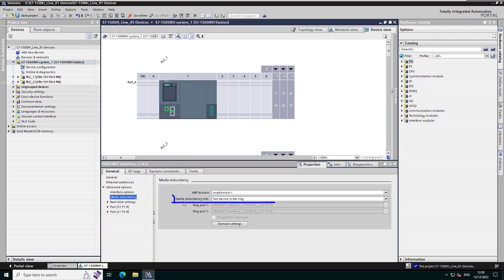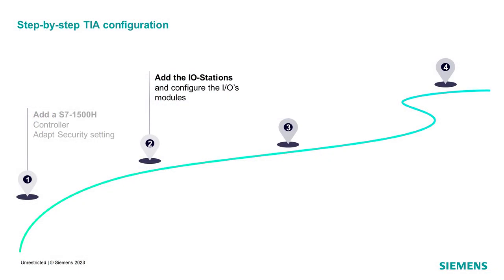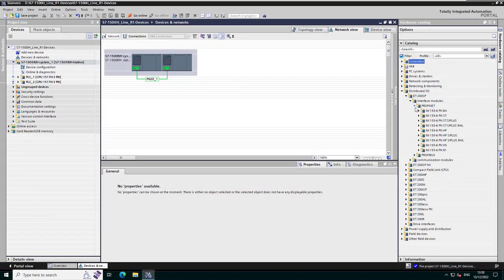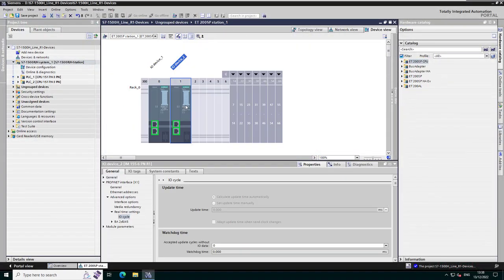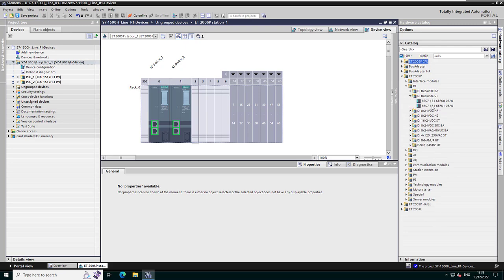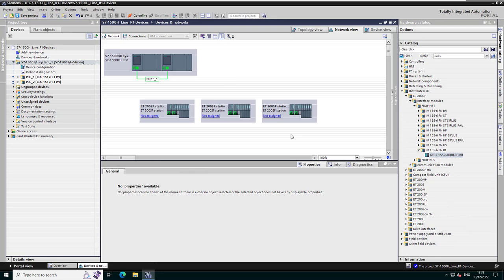To be noted: the default MRP configuration is not device in the ring, therefore there is by default no MRP configuration for each controller. Step 2: add and configure your R1 devices. Here is an example — one station ET200SP with redundant interface and the I/O module configuration. The three R1 devices are now configured.